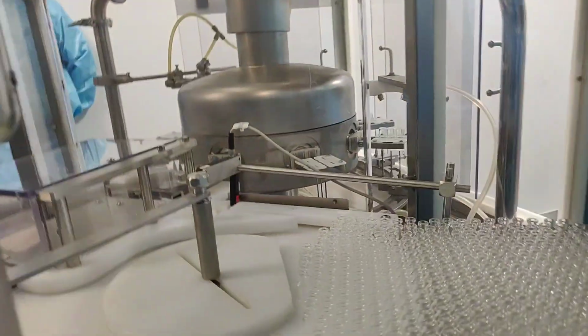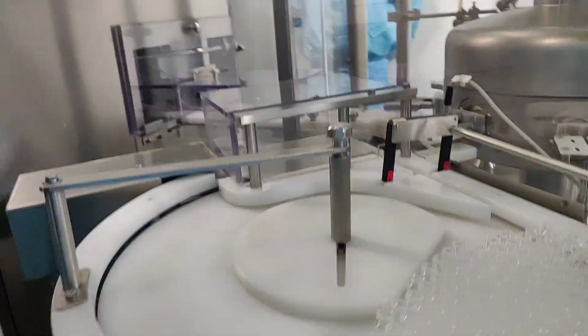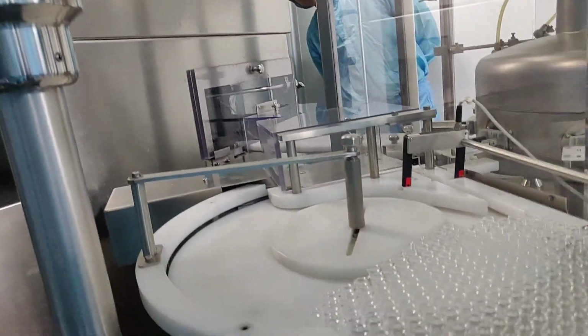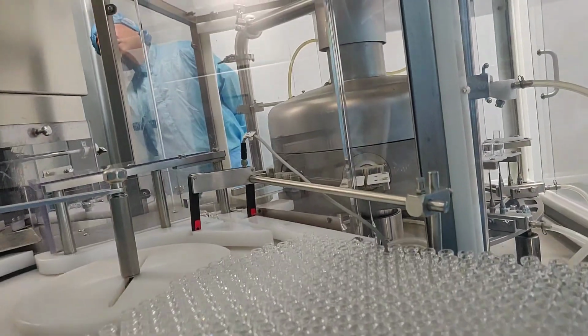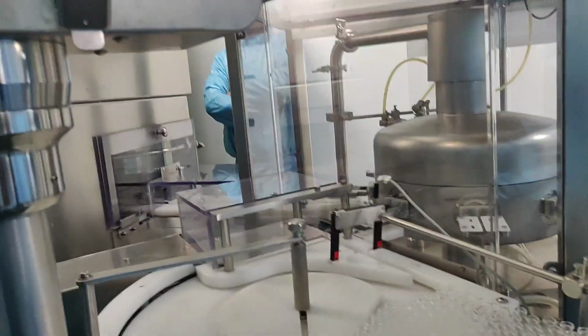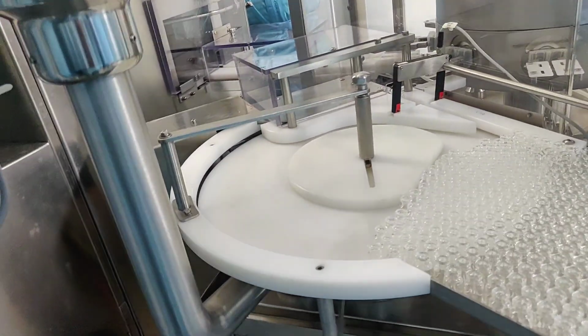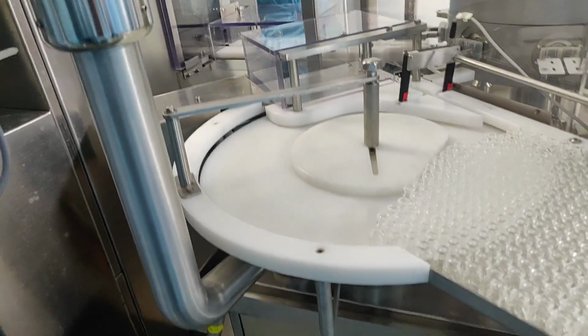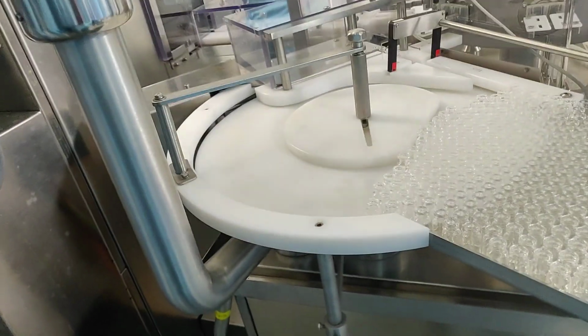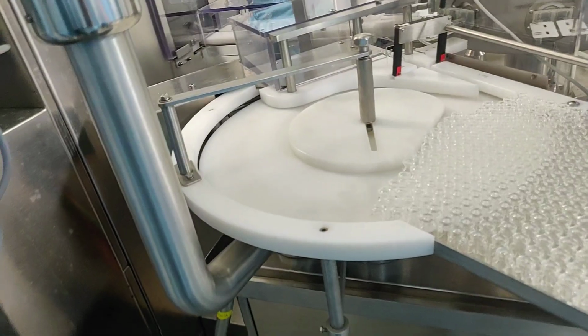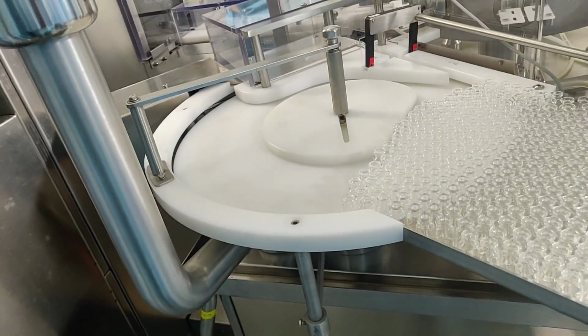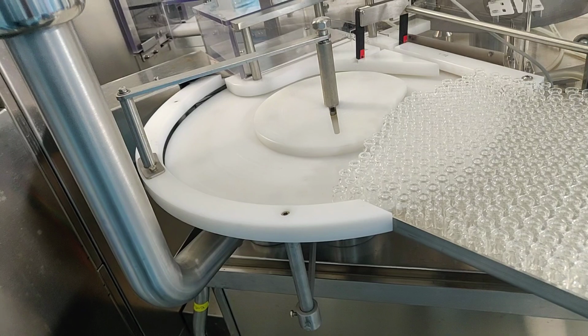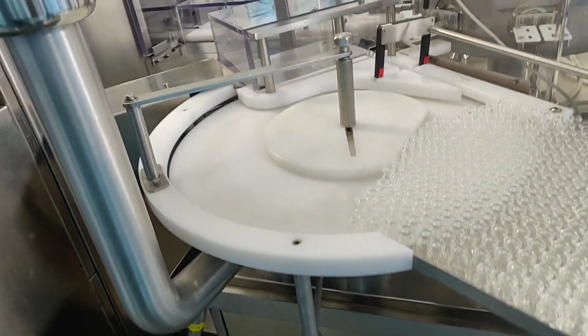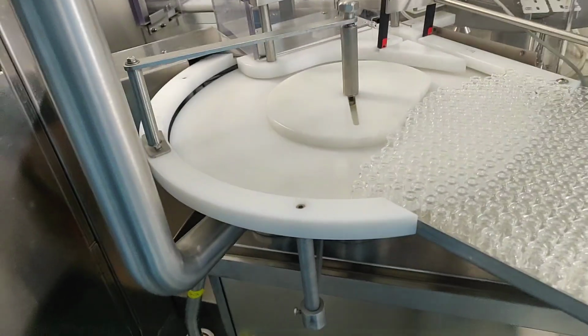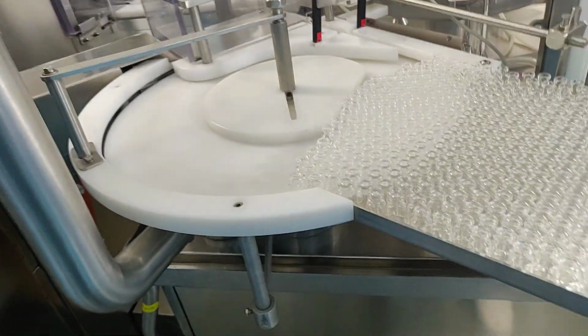Now I have another question. Tunnel sterilization at 300 degrees, and the cooling zone connects to the filling machine. So what is done here is not just sterilization, it's also depyrogenation, right? Because for sterilization you just need 122 degrees for maybe 10 to 15 minutes at most, but for depyrogenation you need to go over 250 degrees. So most probably you are doing both sterilization and depyrogenation at the same time. Okay, it's clear.